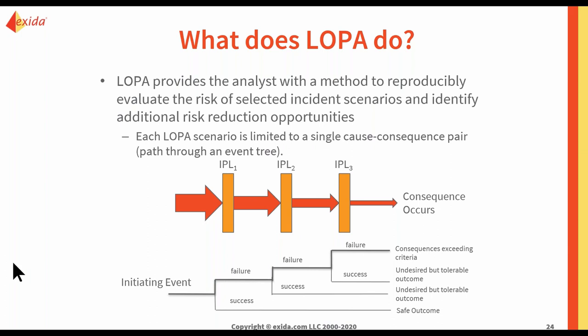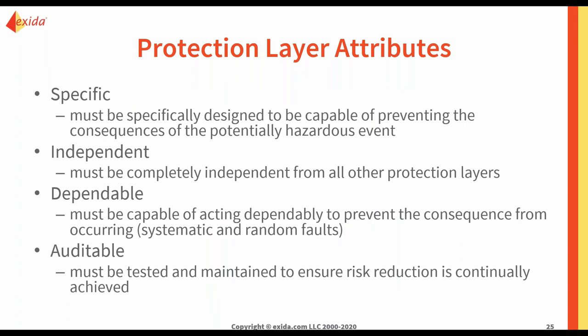But about the IPLs, we actually need to look at them differently. There are different criteria the IPLs need to fulfill in order to be a valid IPL. First of all, it has to be specific. It has to be specifically designed and be capable of preventing the consequences. If it is not specific to this hazard, we cannot really count on it. For example, if there is a situation of overpressure of a vessel, but you are trying to take a high temperature alarm, it might actually work, but it's not specific to this particular hazard. So that is not a valid IPL over here.